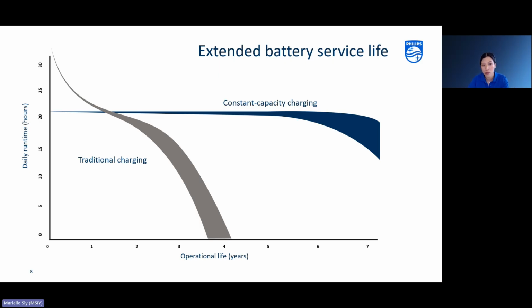We expect that to be around 5 years without experiencing any significant drop or needing the battery to be replaced. So this is our expectation. So for your clients, the practical message is don't worry if the HearLink 50 doesn't last for 30 or 40 or 50 hours, because it is meant to function like that. It is reserving the battery life and it's working as designed. So they will have a much more consistent experience throughout the years to come.